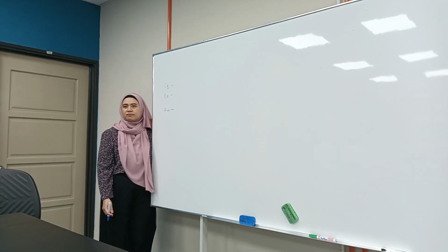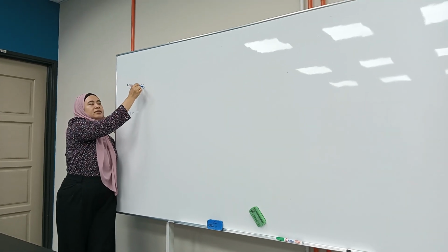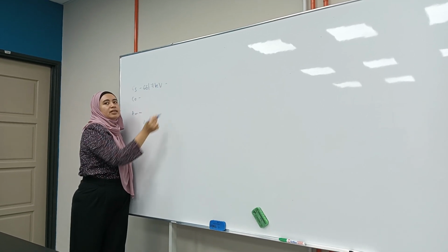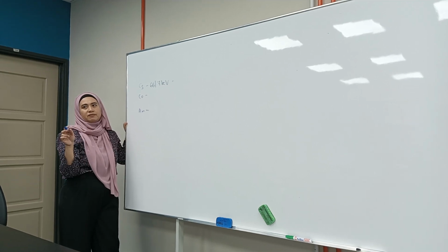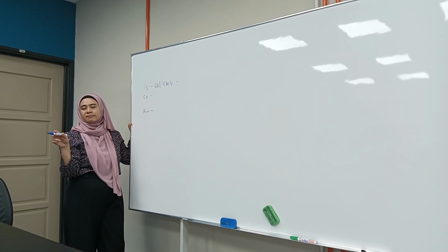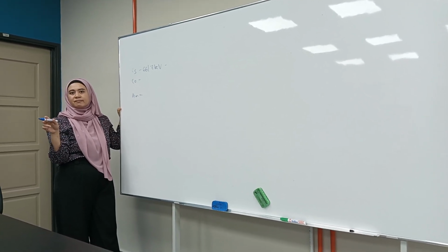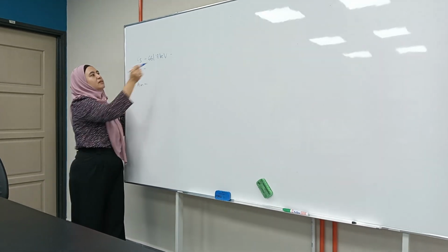You guys have all this information, correct? We've done a demo in the lab. We started with cesium. What's the energy for cesium? 661.7 keV. And we have the channel number. What's the channel number for cesium? 331.48.